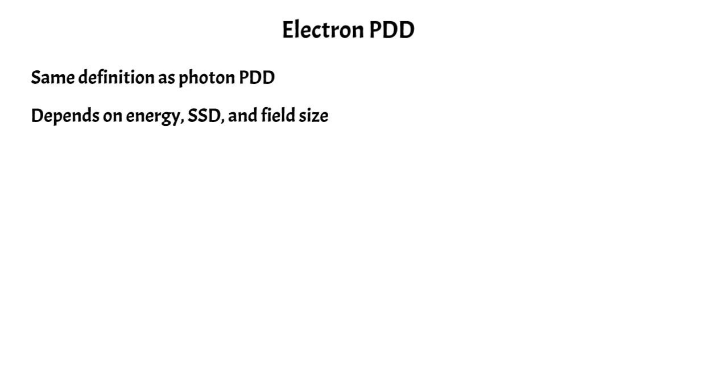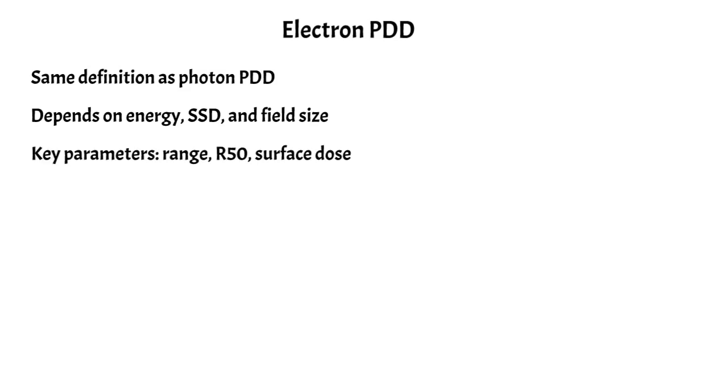It does have a few similar dependencies as well. It depends on the beam energy, the source to surface distance, and also the field size that you are measuring the PDD at. Some key parameters that define the PDD include the range, the R50, which is the range at which the dose drops to 50 percent of its maximum value, and also the surface dose.